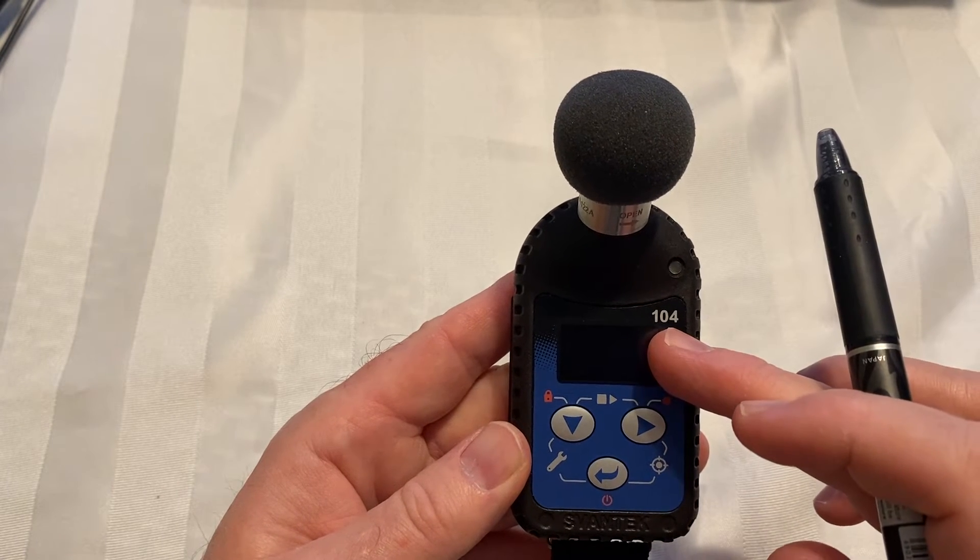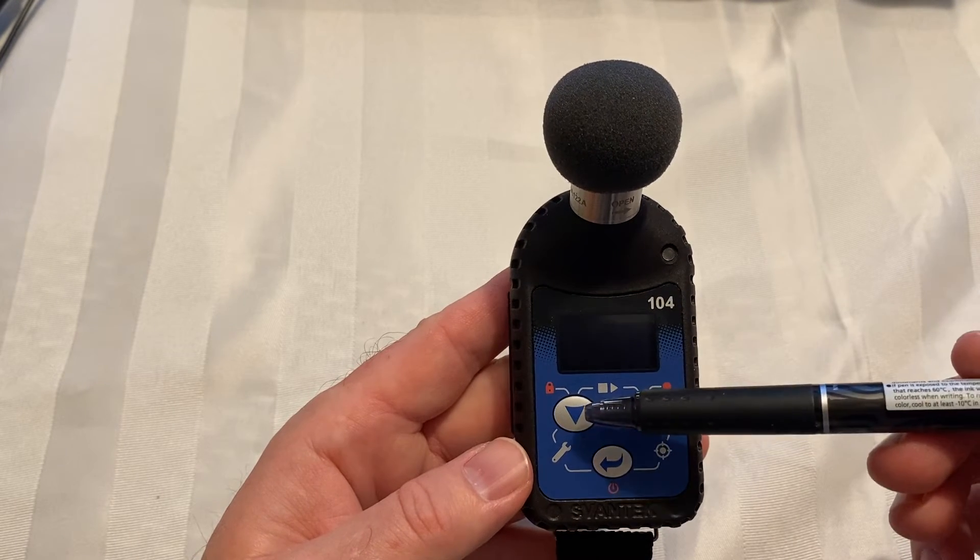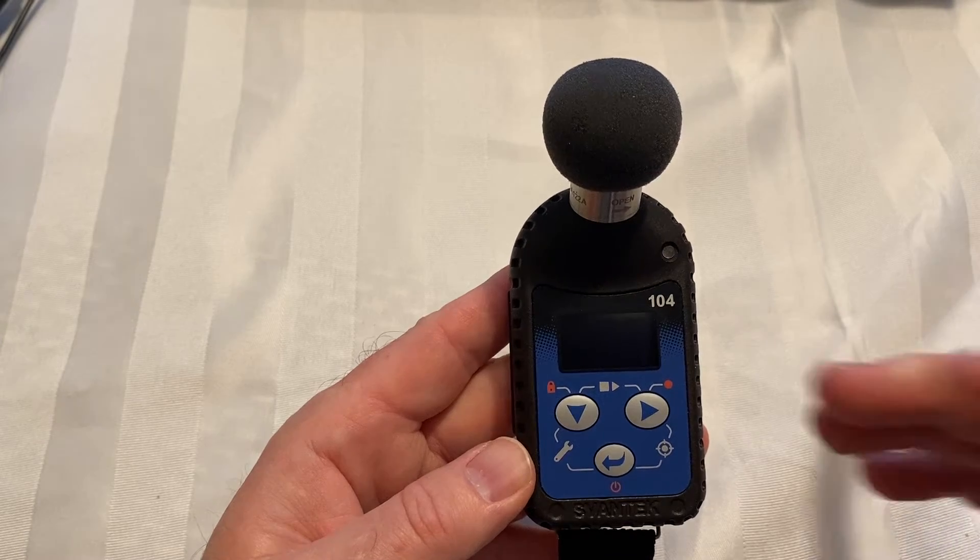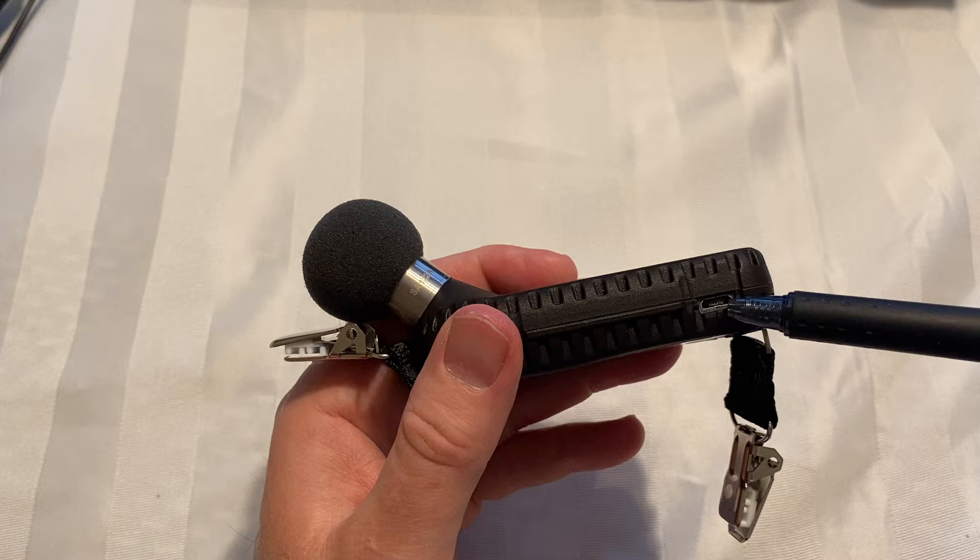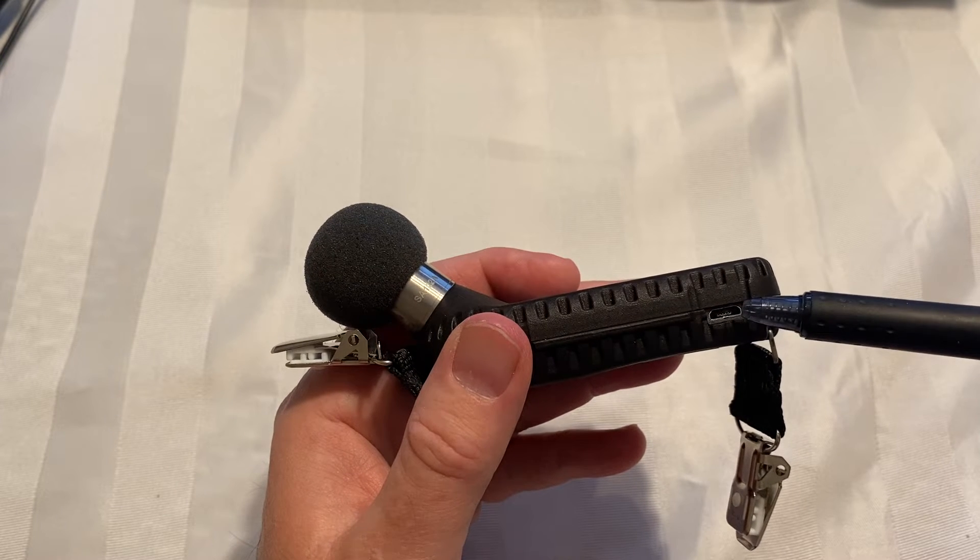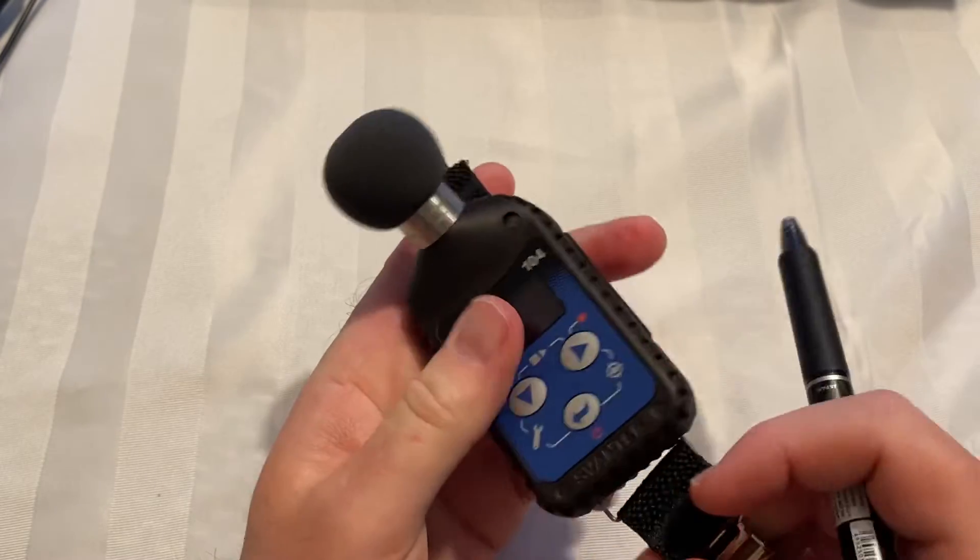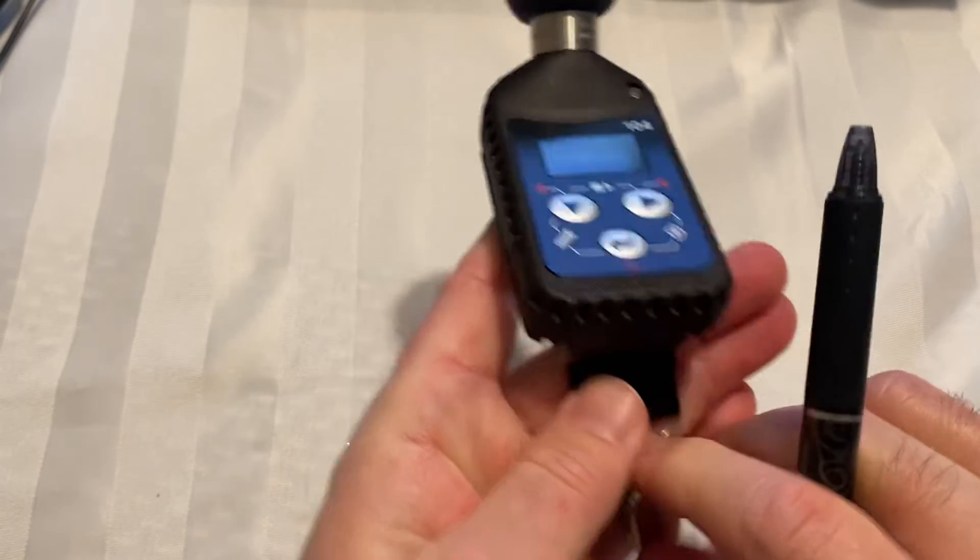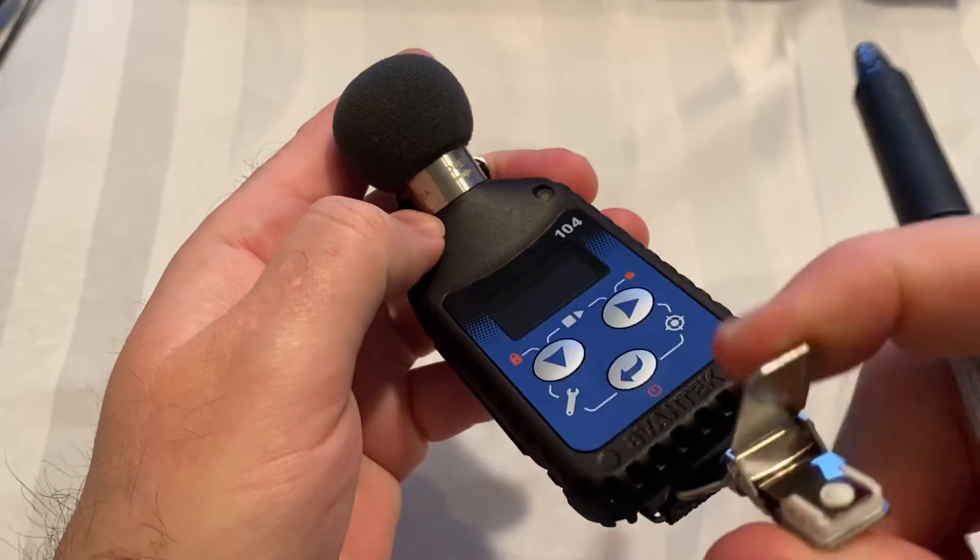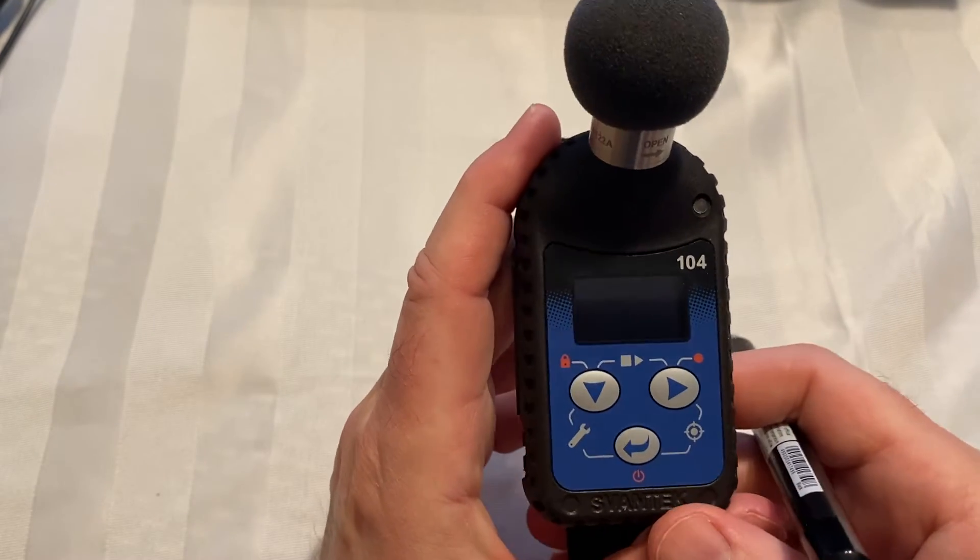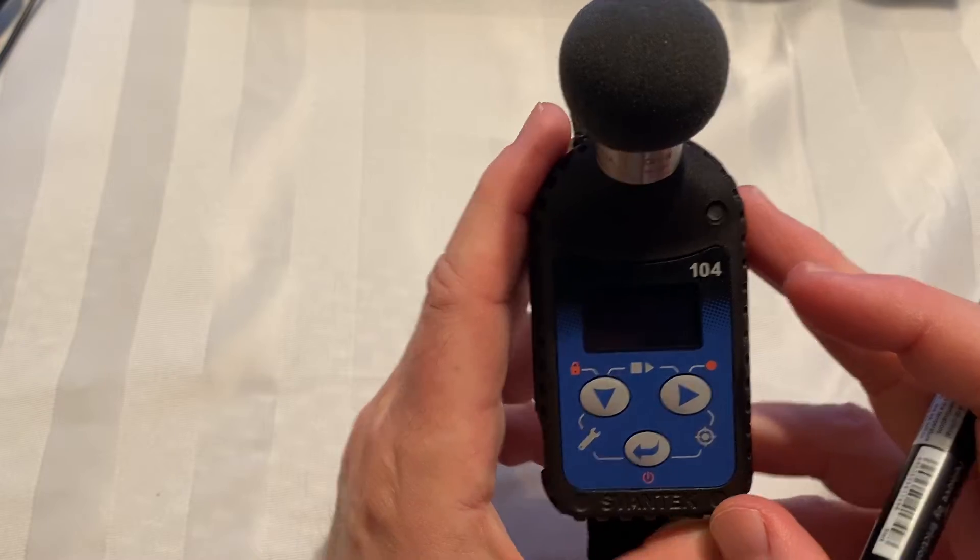This is the color display and we have three buttons: the down, right, and enter button. On the side there's the connection for the USB cable to charge, download the data, and configure the dosimeter. There's also suspender clips on either end that open up and can be used to attach the dosimeter to the person being monitored - on their shoulder, close to the ear, is where it should go.